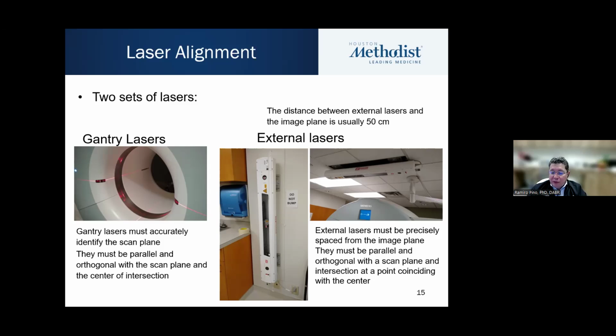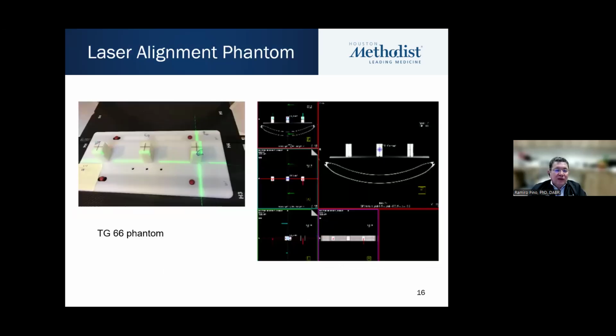Obviously, all of them need to be QA'd. Typically, we have requirements in terms of positioning and motion. This is one of the phantoms. It's called the TG66 Phantom, which is because it's associated with the TG66 report, and basically has some accurate positioning and markings that you can use to test all the laser motions and often the couch motions as well.